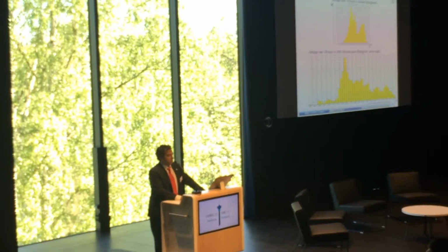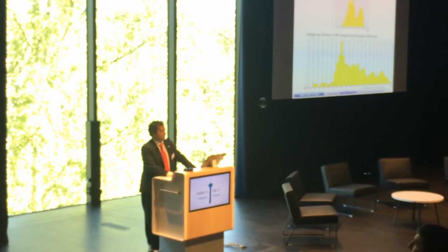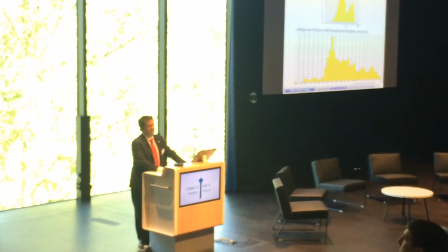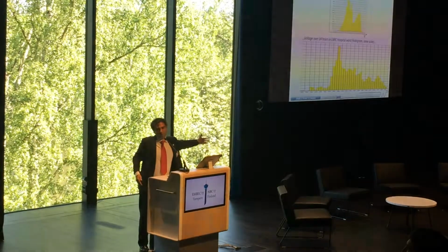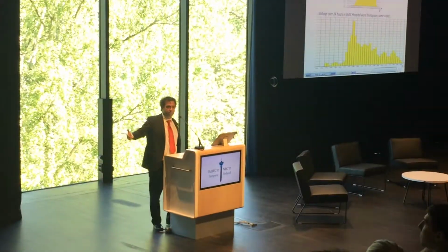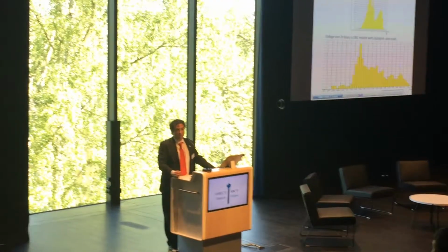Okay, that's the same information, as a histogram. For you to know, this is the same scale. So we have 220 plus or minus 5 in Europe, and here we have something which goes from 150 to 350, which is obviously dangerous for the device, for the operator, for the patient.